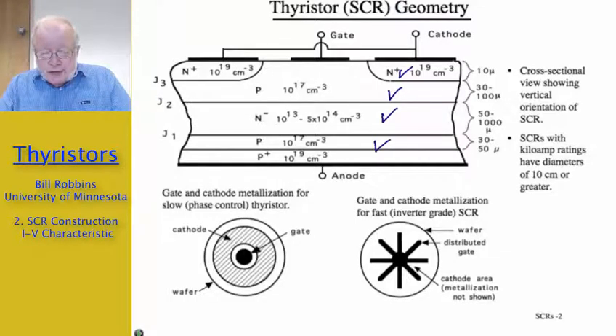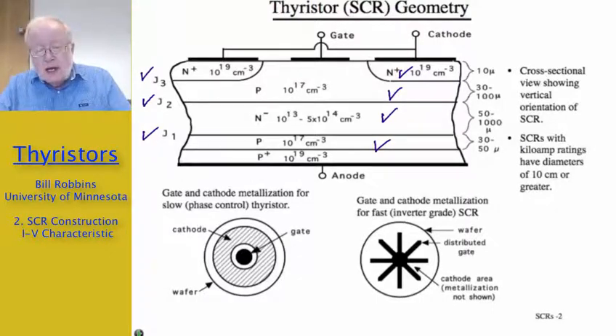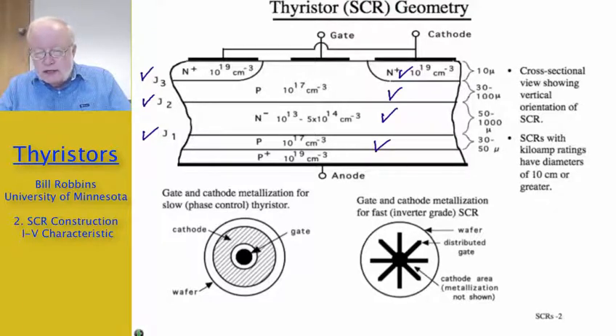In conjunction with this four-layer structure, there are three P-N junctions that we need to be aware of. I've labeled them J1, J2, and J3, and we'll discuss them in more detail in the next few slides. The typical doping levels and thicknesses of the different layers are shown in the drawing. The N-minus layer is very lightly doped, 10 to the 13th to 10 to the 14th, and its thickness can range from a few tens of microns to upwards of a thousand microns, depending on the rated breakdown voltage.